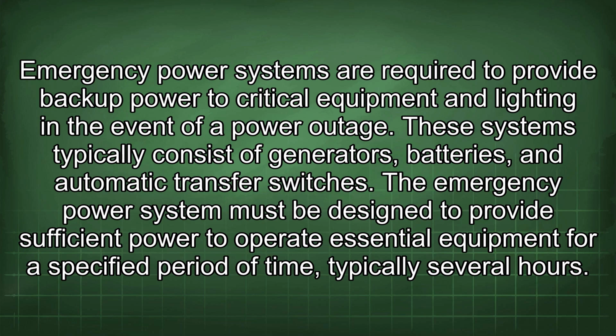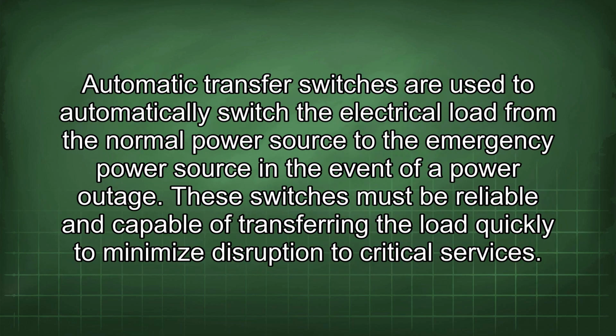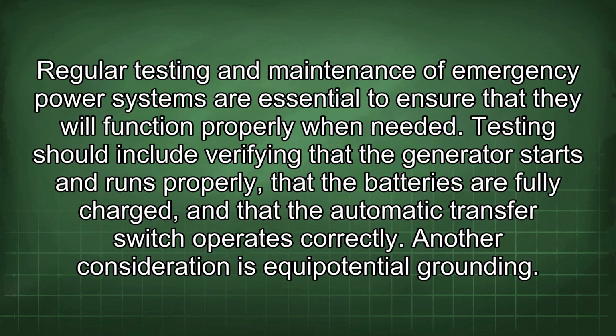Emergency power systems are required to provide backup power to critical equipment and lighting in the event of a power outage. These systems typically consist of generators, batteries, and automatic transfer switches. The emergency power system must be designed to provide sufficient power to operate essential equipment for a specified period of time, typically several hours. Automatic transfer switches are used to automatically switch the electrical load from the normal power source to the emergency power source in the event of a power outage. These switches must be reliable and capable of transferring the load quickly to minimize disruption to critical services. Regular testing and maintenance of emergency power systems are essential to ensure that they will function properly when needed. Testing should include verifying that the generator starts and runs properly, that the batteries are fully charged, and that the automatic transfer switch operates correctly.